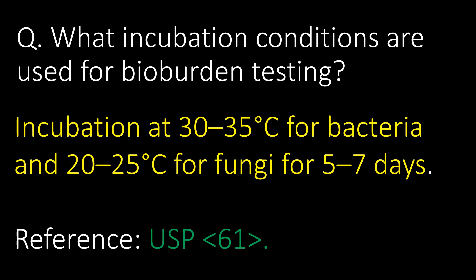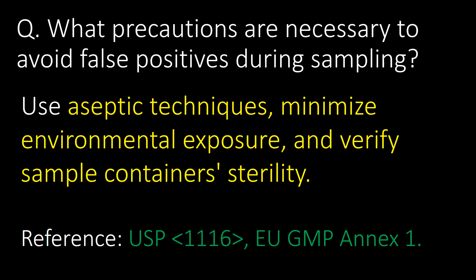What incubation conditions are used for bioburden testing? Incubation is at 30 to 35 degrees Celsius for bacteria and 20 to 25 degrees Celsius for fungi, for 5 to 7 days. Reference USP Chapter 61. What precautions are necessary to avoid false positives during sampling? Use aseptic techniques, minimize environmental exposure, and verify sample container sterility. Reference USP Chapter 1116 and EU GMP Annex 1.